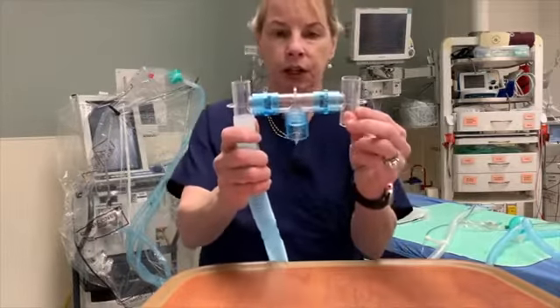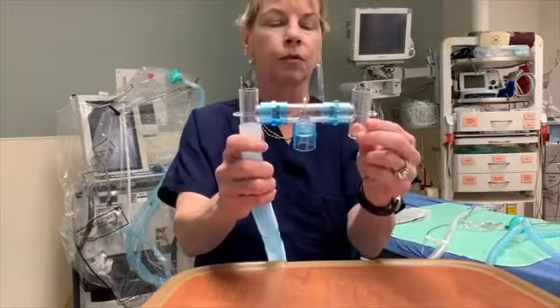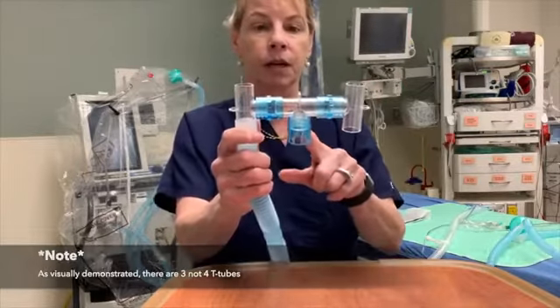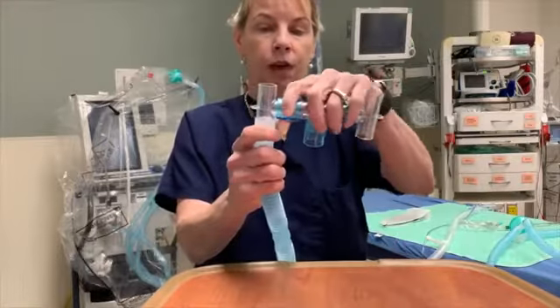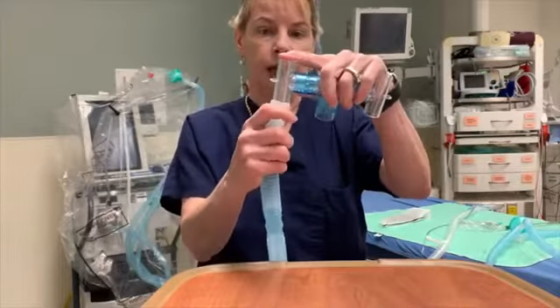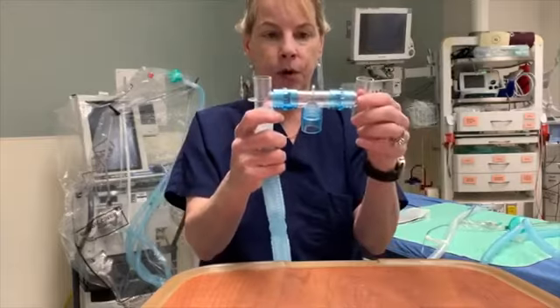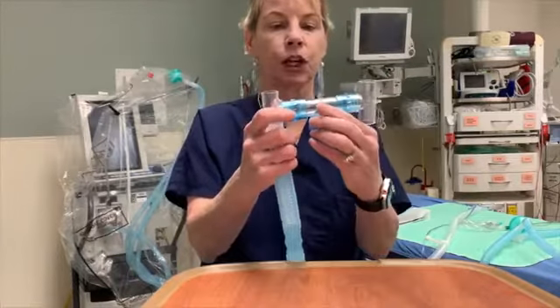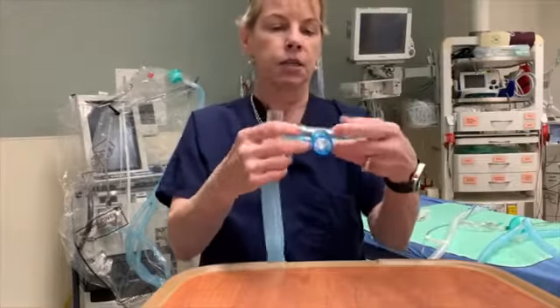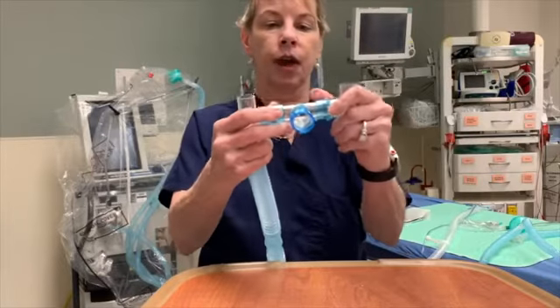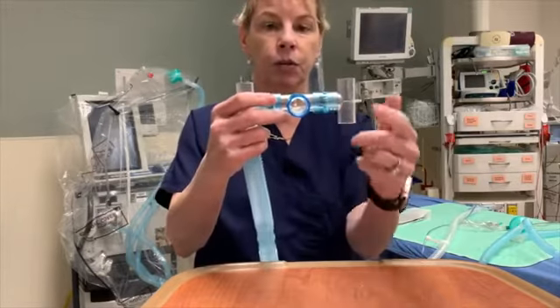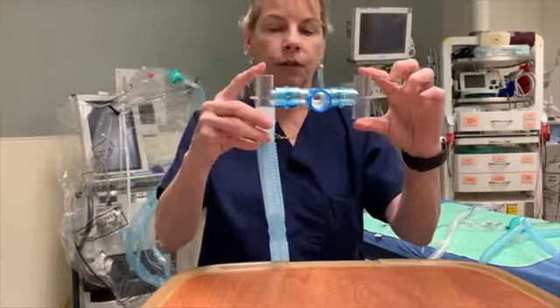You would need two of these circuits, one for the inspiratory circuit and one for the expiratory circuit. It has 4 T-tubes and it has 3 22mm adapters. And for the inspiratory cycle or the expiratory cycle, you simply add the patient to the port. Obviously, if you're going to use this in the patient situation, you would rotate it 90 degrees so that the ventilator port is going directly towards you, and then these 4 ports are for the patients.